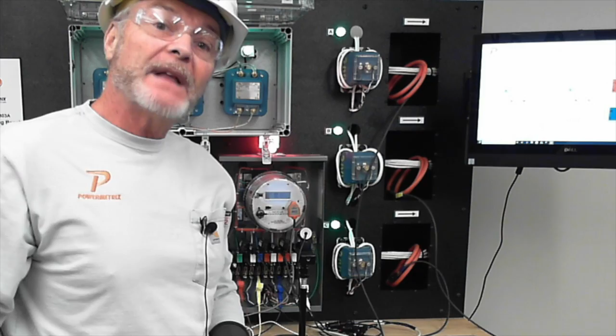So if I've got A, B, and C phase, let me do it this way so y'all can see it. If I have it like this, think about it - I can run that same conductor on B phase through both. I can use two flexes, put one up here like this and one down here like this, so I have B phase running through both CTs, but one runs one way and one the other, so they cancel out and it's used as a reference.